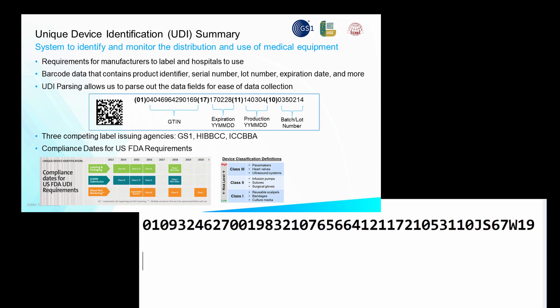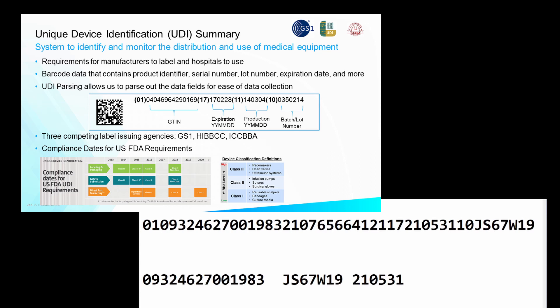For reference, on the left I've put up a UDI summary to remind everyone watching what we're talking about regarding the code and the number. Now I'm going to scan a code raw, without any formatting on it. As you can see, it's just basically one string of data — no modification of any type — including the ID codes from each segment of the barcode. For example, the '01' indicates a GTIN, which is the GTIN value shown here. Now I'll scan it with a scanner that has been programmed with the parsing code as we did in 123Scan. What you can see is that it's followed exactly what we asked it to do: it hasn't forwarded the ID codes because we didn't ask it to, it's added a tab between the GTIN, lot number, and date of manufacture, and it has also sent an Enter key at the end to forward to the system. So it's basically done everything we asked it to do.